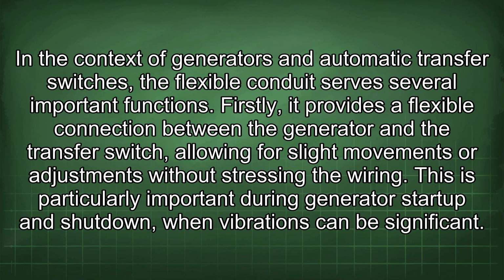In the context of generators and automatic transfer switches, the flexible conduit serves several important functions. Firstly, it provides a flexible connection between the generator and the transfer switch, allowing for slight movements or adjustments without stressing the wiring.